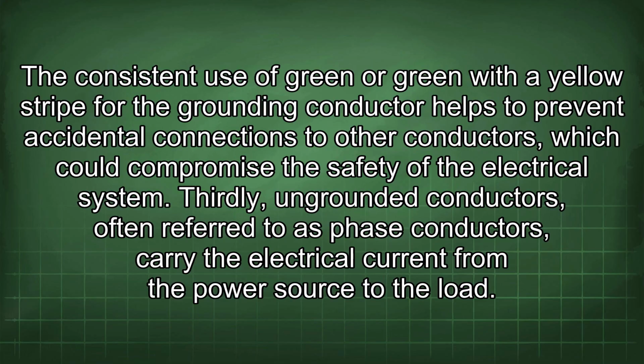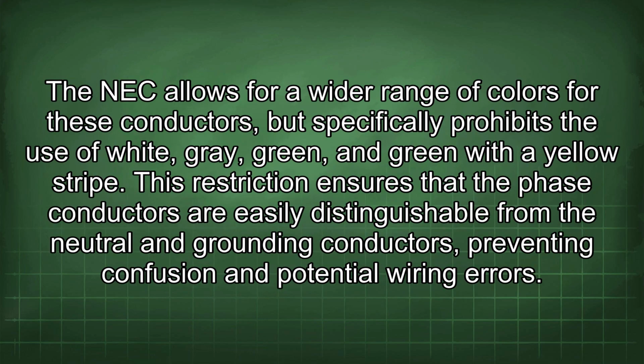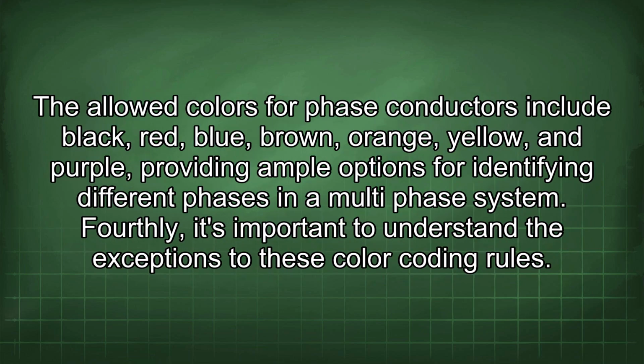Thirdly, ungrounded conductors, often referred to as phase conductors, carry the electrical current from the power source to the load. The NEC allows for a wider range of colors for these conductors, but specifically prohibits the use of white, gray, green, and green with a yellow stripe. This restriction ensures that the phase conductors are easily distinguishable from the neutral and grounding conductors, preventing confusion and potential wiring errors. The allowed colors for phase conductors include black, red, blue, brown, orange, yellow, and purple, providing ample options for identifying different phases in a multi-phase system.